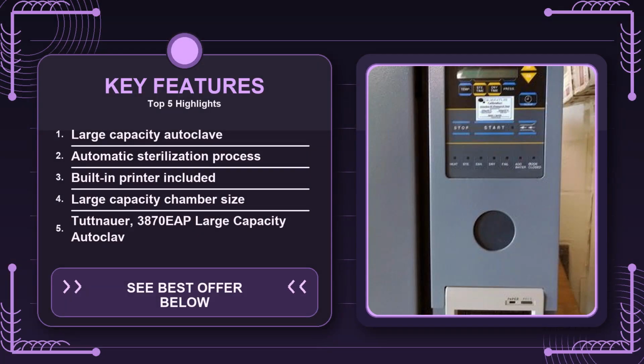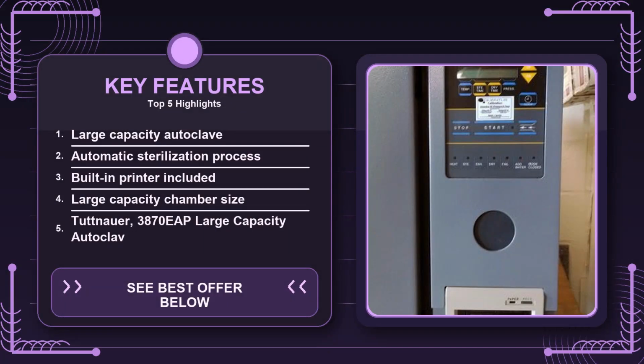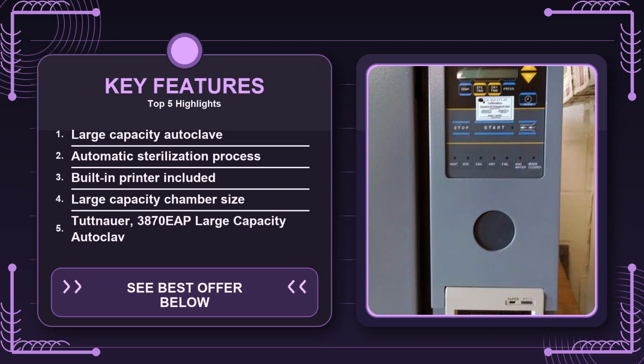First off, let's talk about the real-world scenario most people face. In a busy dental practice, you might be pulling out trays every few minutes, trying to keep up with patient flow while still meeting strict infection control standards. The 3870EAP's large chamber lets you load a full set of instruments in one go, which cuts down the number of cycles you need to run each day. That translates into real time saved on the back-of-house side and a lower cumulative energy draw because you're not heating up a small chamber over and over again.